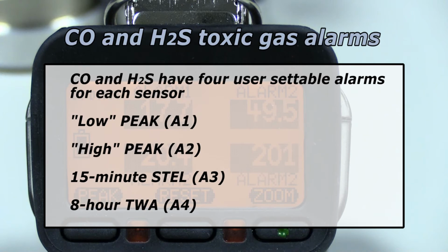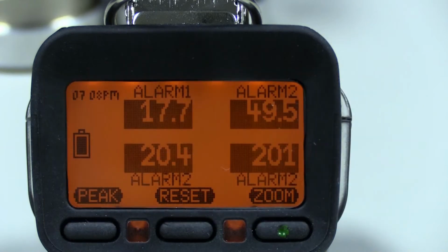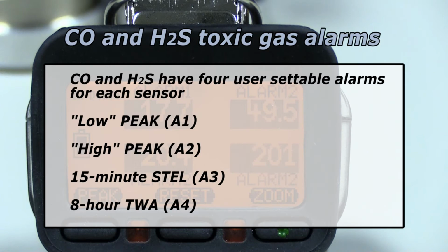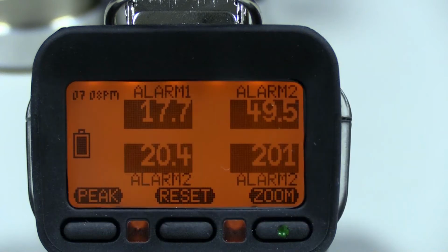The low peak alarms and the high peak alarms are based on the moment-to-moment real-time concentration. If the reading is higher than the alarm setting, the alarm is immediately sounded. The STEL alarm is calculated on a 15-minute basis. The TWA alarm is calculated on an 8-hour basis. The STEL and TWA alarms are used to guard against exposure that occurs at lower concentrations but continues over a longer period of time. The G450 is capable of detecting gas at very low concentrations.